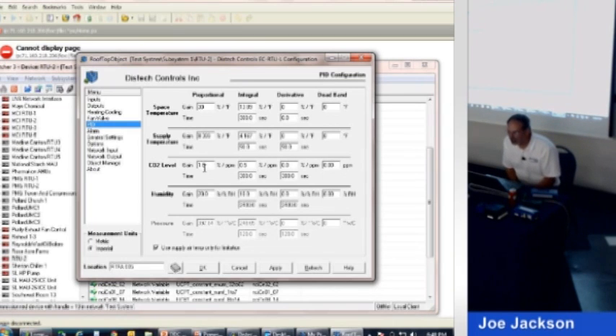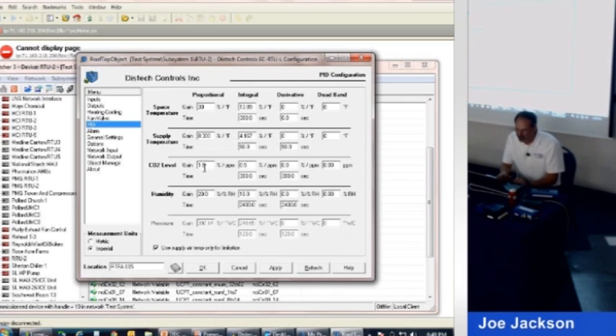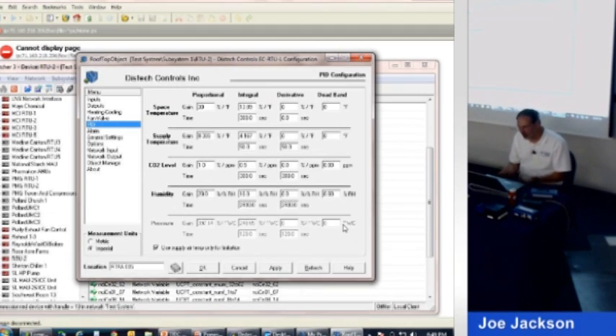There is math that goes on behind it. You could actually calculate all of these things. To be honest with you, I don't know how to do it. If for some reason we did have to change one, all I'd do is, if things were hunting up and down, I'd increase the integral time, and things would probably stabilize right off the bat. I might take 2 or 3 guesses, and we'd stabilize it. The only one I've ever had to change is if you have a fan with a VFD on it. I think I have played with a couple of these numbers to get the fan to stabilize, but generally you don't have to do that.